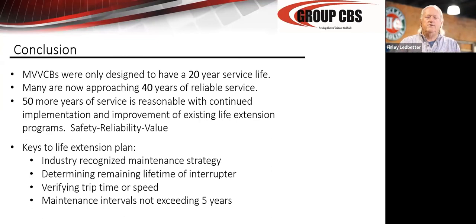Basically, their breakers were originally designed for a 20-year life. I don't believe that, but that's what it says. That was the salespeople talking, because the salespeople want it out every 20 years and they want you to buy new switchgear. I think the switchgear will survive 100 years, okay, 100 years plus, and it has to today because we don't have anything to replace it. There's no silver bullet coming quick right now that's going to replace vacuum breaker technology. So we have to keep this gear in service.